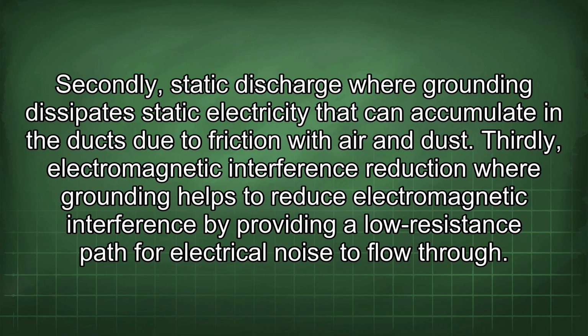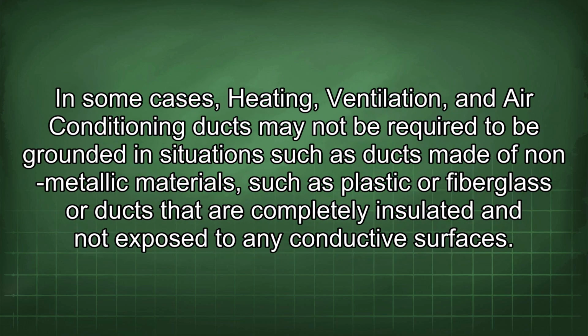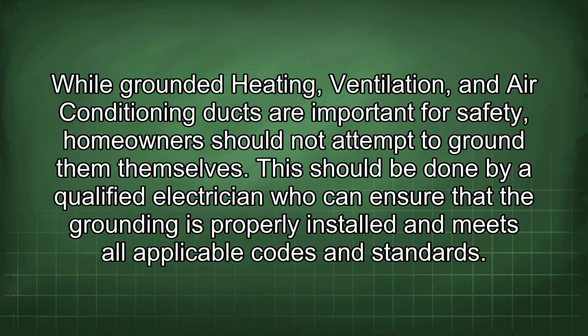In some cases, heating, ventilation, and air conditioning ducts may not be required to be grounded, in situations such as ducts made of non-metallic materials, such as plastic or fiberglass, or ducts that are completely insulated and not exposed to any conductive surfaces. While grounded heating, ventilation, and air conditioning ducts are important for safety, homeowners should not attempt to ground them themselves. This should be done by a qualified electrician who can ensure that the grounding is properly installed and meets all applicable codes and standards.